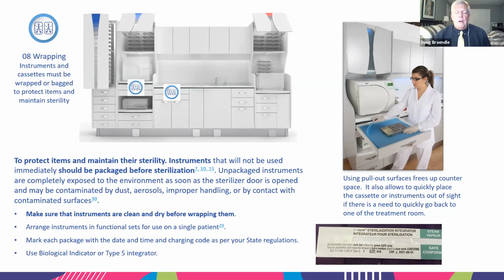So if you are running a practice and everything has always been fine, but this one Thursday comes up, and Thursday is your day to do the BI. So the following day you're in the office on Friday and you find out from the incubator, we had a failure. Well, CDC basically says, in order to verify a failure, we need to do 2 BIs back to back. So hopefully you have Saturday hours, you do another BI, and if in that case you have another failure, then you isolate the instruments that you can, and you take that machine out of service.